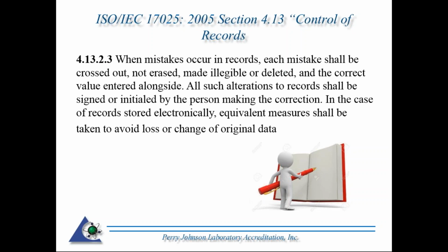If you make a mistake, or if during the review of the certificate, the data sheet, there's a lot of erasing, well, that's prohibited. But scribbled items being crossed out without the audit trail being followed, which specifies the date and initial of the person who made the changes, that is subject to a non-conformance. And again, that's something that's seen.